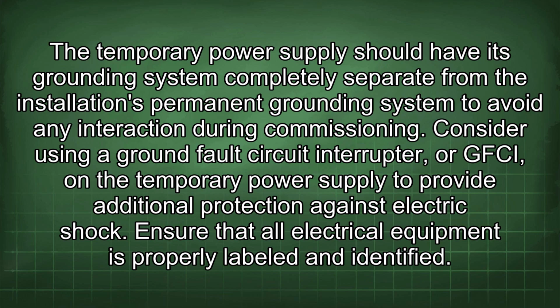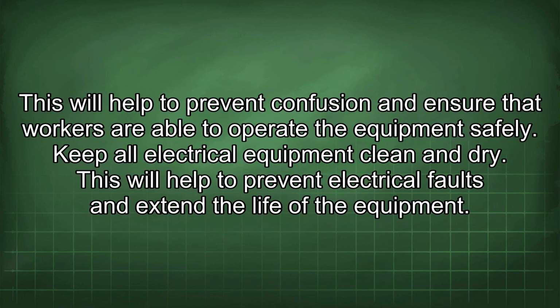Consider using a ground fault circuit interrupter, or GFCI, on the temporary power supply to provide additional protection against electric shock. Ensure that all electrical equipment is properly labeled and identified. This will help to prevent confusion and ensure that workers are able to operate the equipment safely. Keep all electrical equipment clean and dry. This will help to prevent electrical faults and extend the life of the equipment.